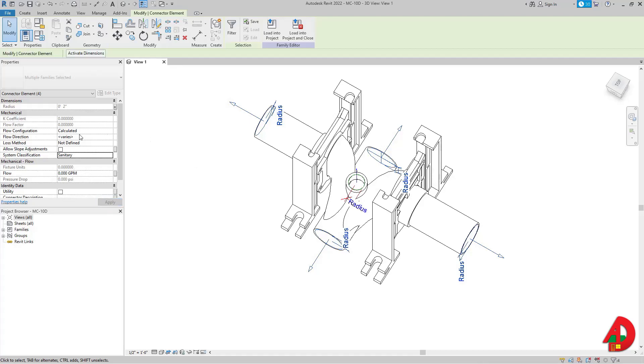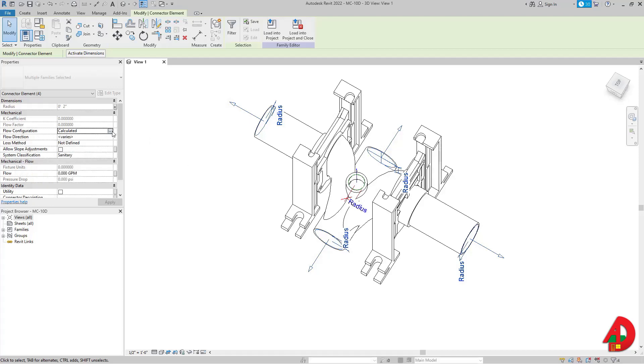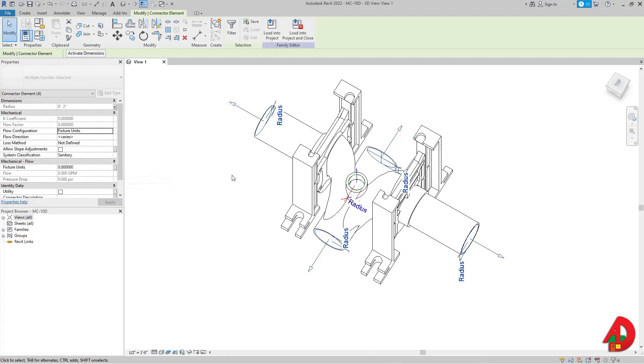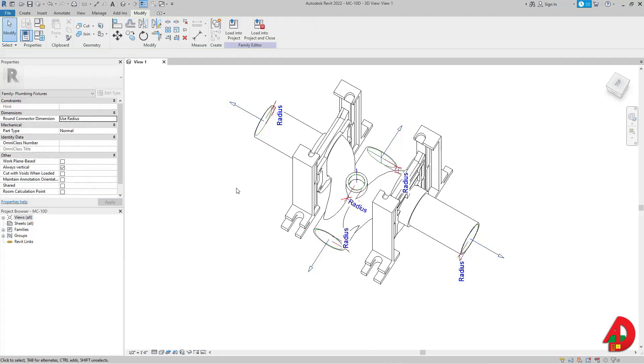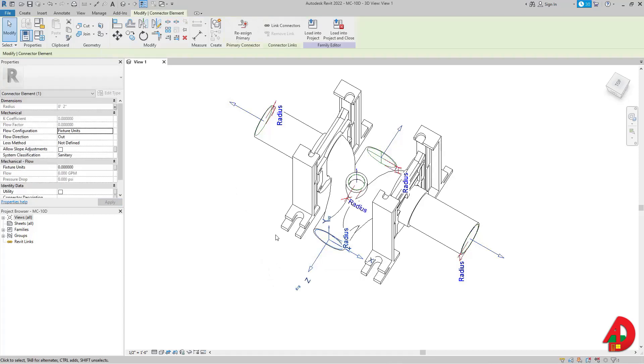The reason they're grayed out is because flow configuration is set to 'Calculated.' I have to set it to 'Fixture Units,' and now fixture units become editable. I'll hit Escape twice. Since all connectors' flow configuration is set to Fixture Units, I'm not going to change the fixture units value directly, because this value will be set by the water closet.